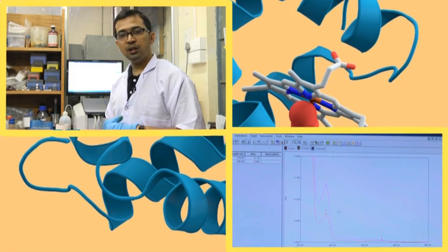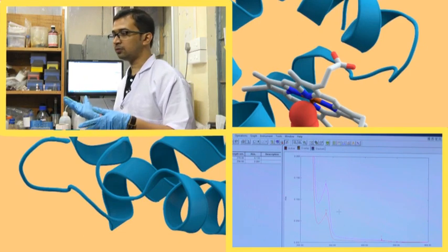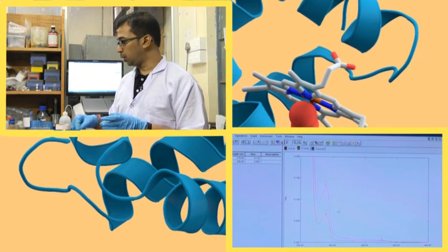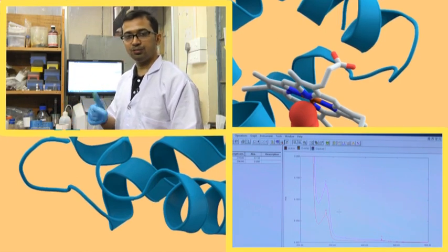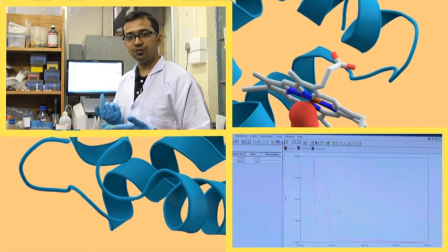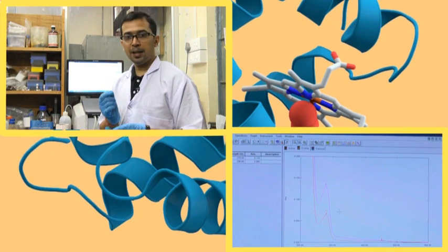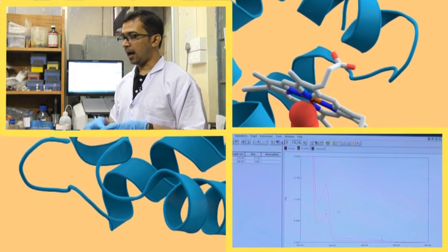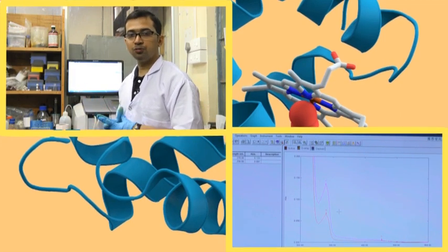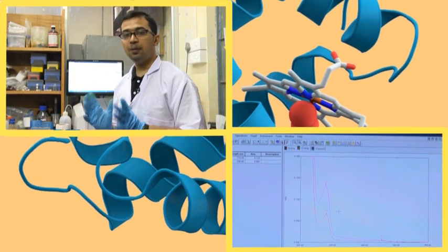So, you can proceed with this method if you feel like, or in some advanced UV machines there is a magnetic stirrer attached to it. So, you take a cuvette, that is much more reliable and much more accurate. As we can see in the cuvette holder, there is a magnetic stirrer. Magnetic stirrer is common in the lab, but this one is at a micro scale level. In the cuvette we put a small magnetic bit, generally known as rice bit, in such a way that it does not break the cuvette, and just turn on the switch on this magnetic stirrer. It will rotate and stir continuously, and it will keep the system homogeneous throughout the reading.